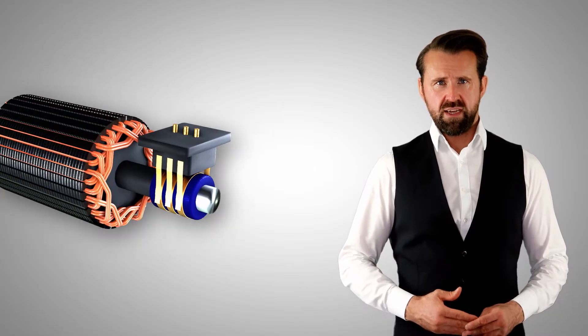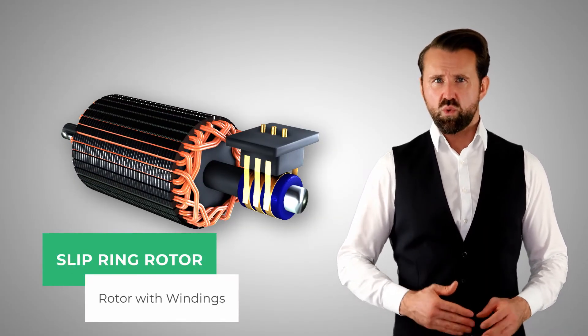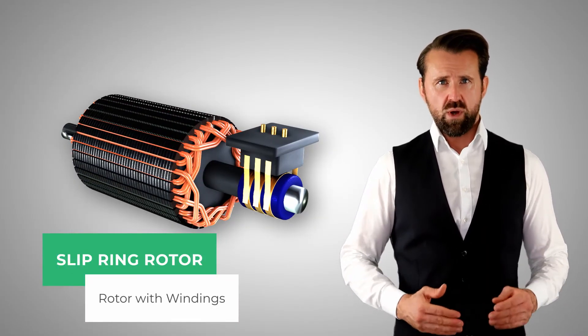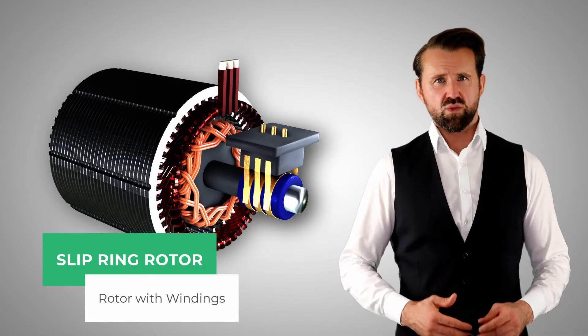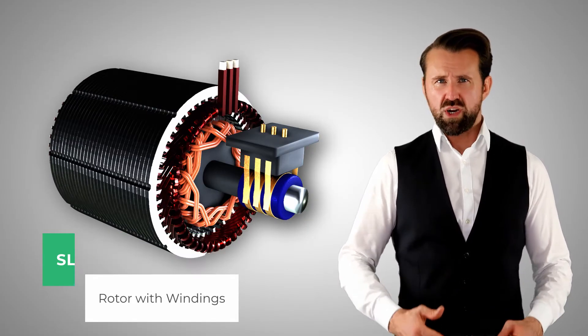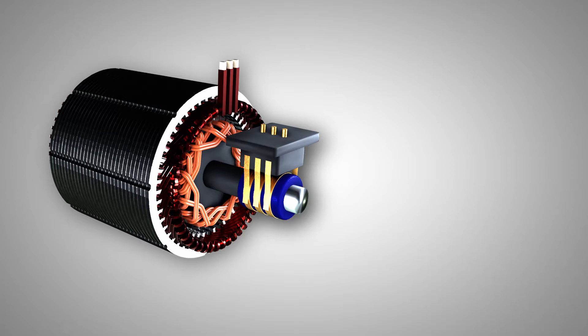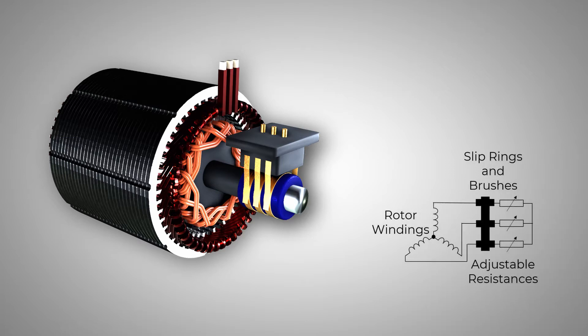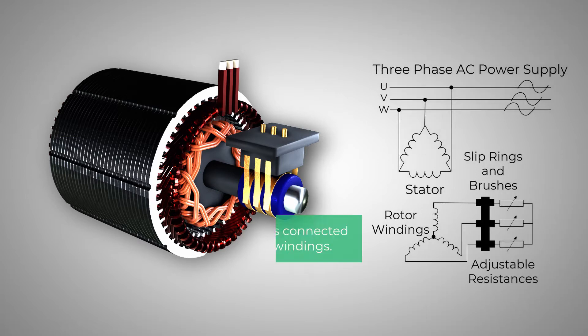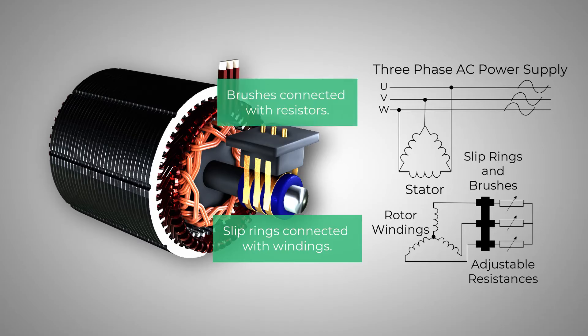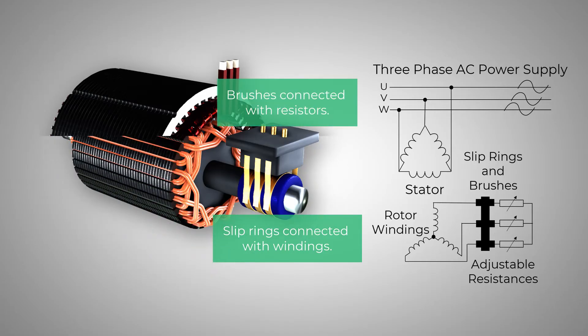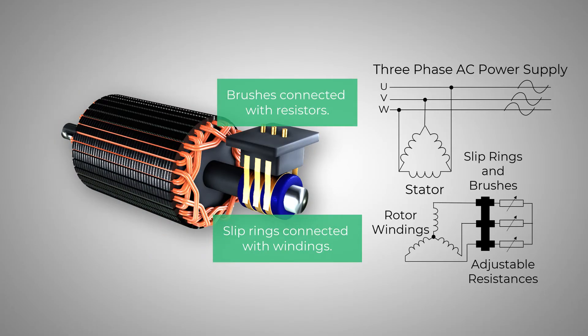The second type of induction motor is a slip ring rotor. Instead of a short circuit cage, the rotor has windings. The windings in the rotor are connected to three slip rings on which brushes grind. The brushes make contact with variable resistors which are located outside of the rotor. The current in the rotor can be adjusted via the resistors, and therefore the torque can be controlled.